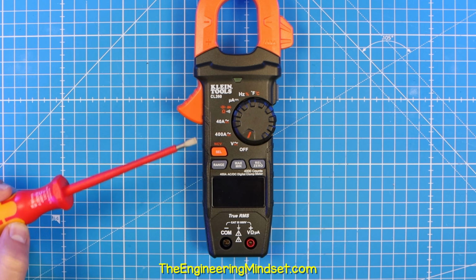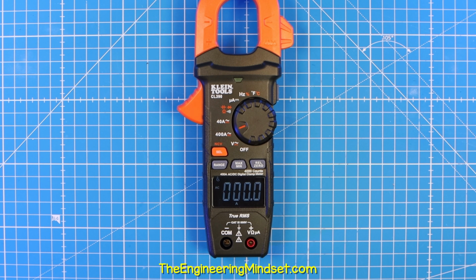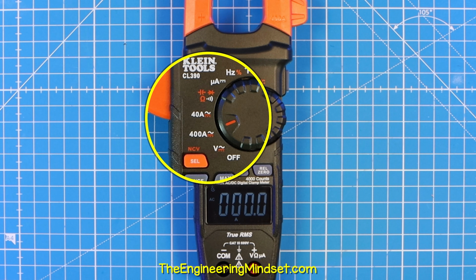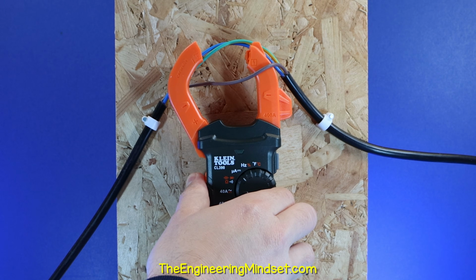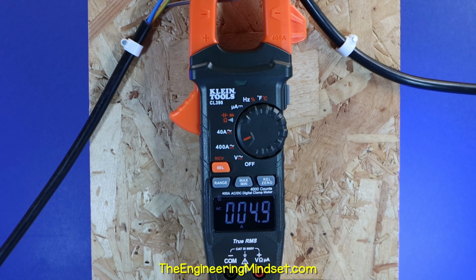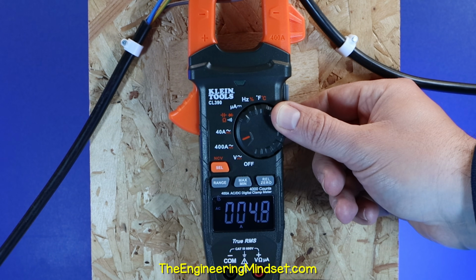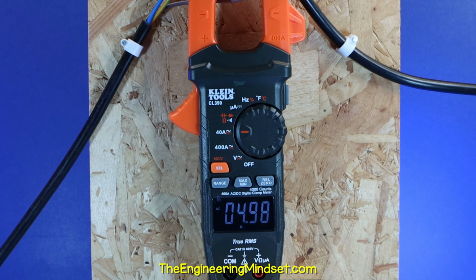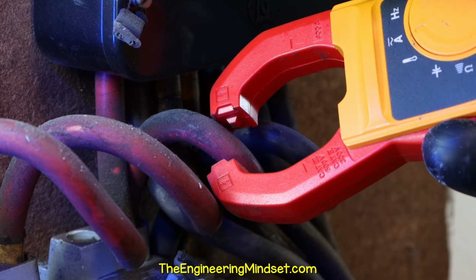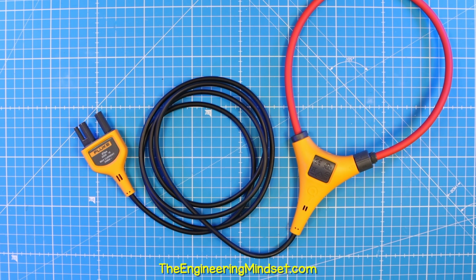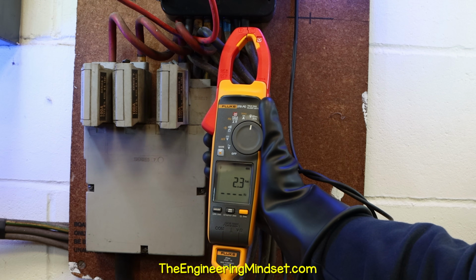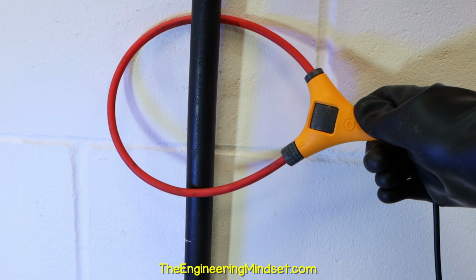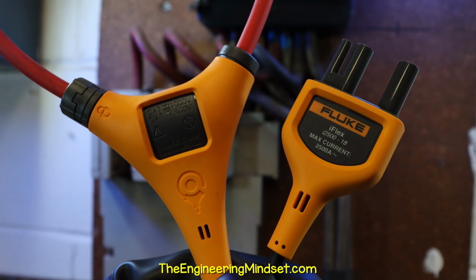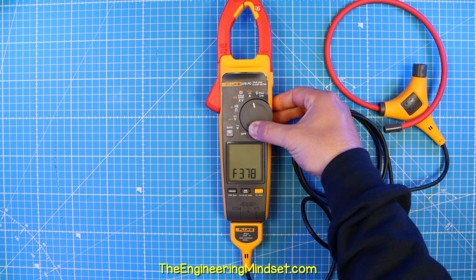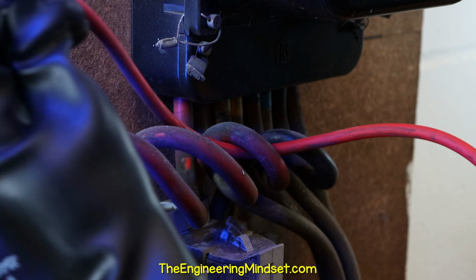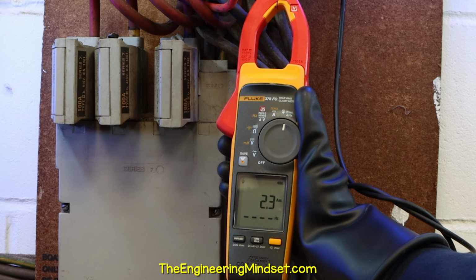If you have a manual range meter, you need to select the appropriate current option. We usually start from the highest option, here that's 400 amps, then clamp around the wire to take a reading. In this example, the current is around 5 amps, so I can switch down to the next level for a more accurate reading. Sometimes it's very difficult to get the clamp into the space. In that case, we can get a flexible clamp which allows us to get a reading. It's also used for large diameter wires, and it can handle a much larger current. We just plug this into the unit, select the iFlex function, clamp around the conductor, and lock the connection. The meter then displays the current value.